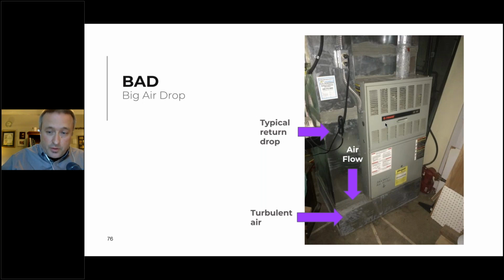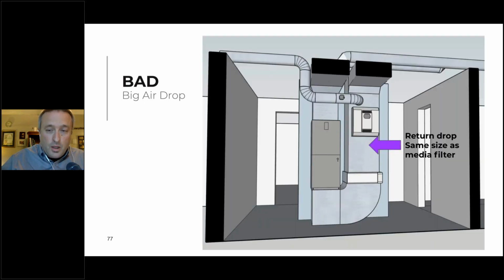This is one of the electrification projects. To fix that, all you need to do is increase the size of the drop—just a bigger duct. What we find is you can size the duct square, the same size as a filter.